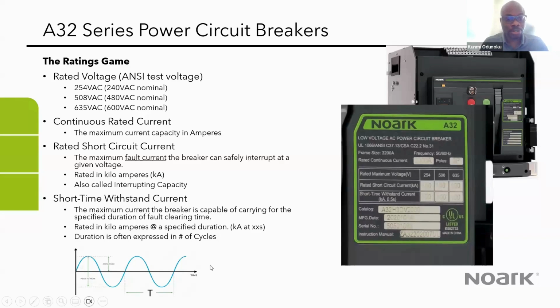So this is measured in number of cycles, and like Rob said earlier, it's 30 cycles, meaning that from this photo we have here, this is a single cycle. That's the time it takes for the voltage and the current to move from the positive half cycle through the negative half cycle. That's one complete cycle. So the withstand capability for the air circuit breaker is 30 cycles, and one cycle is roughly 16.7 milliseconds. So what we are saying is that the breaker is able to withstand that fault for that number of cycles.